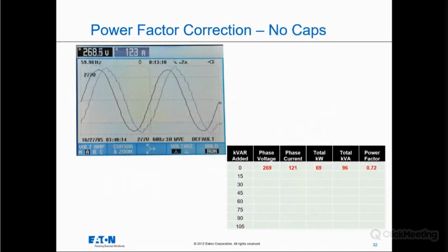So here you can see the waveforms. They're a little bit out of phase with each other. So we can see also below where the phase voltage is 269 volts. The current is 121. Total kW is 69. kVA is 96 and power factor is 0.72. So what do we expect if we add, you can see our increments there in the chart, we're going to add 15 kVAR. What do we expect to happen to the phase current and the kVA?